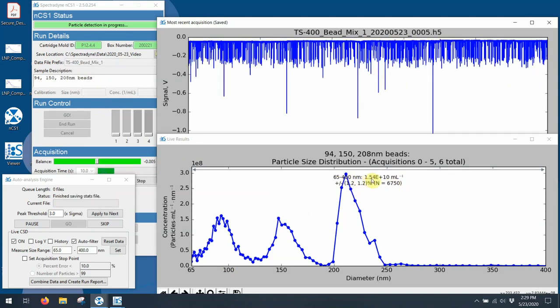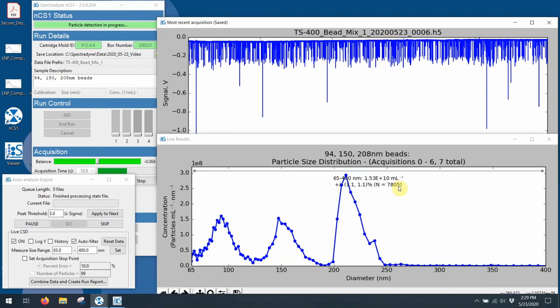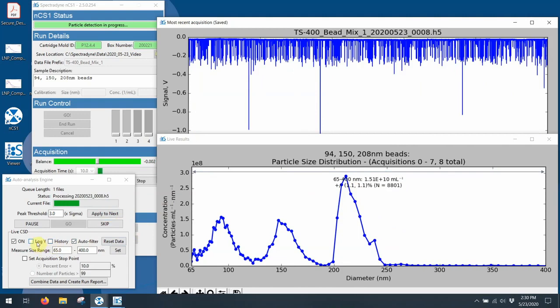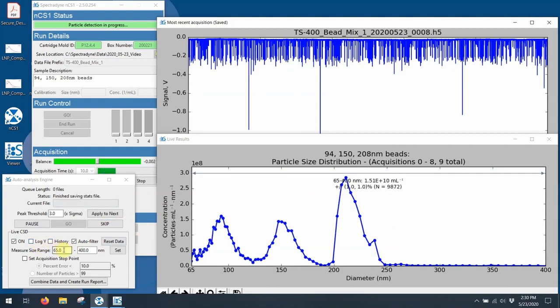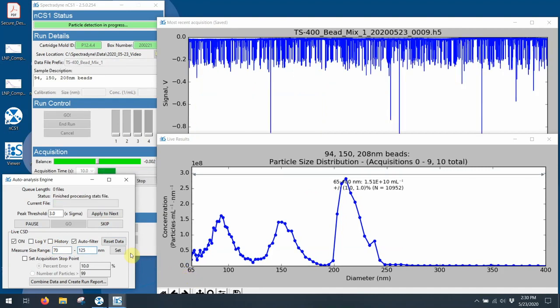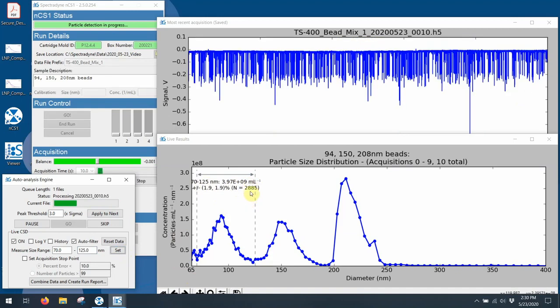Along the bottom here, you can see that it's reporting the overall concentration between 65 and 400 nanometers is 1.54 times 10 to the 10th particles per ml. That there are 6,750 particles that are included in this distribution right now. And this is our counting error, which is based on 1 over the square root of n. At any point in time, I can look at any part of this histogram and see, for instance, the exact concentration of the 94 nanometer beads merely by typing, say, 70 to 125, setting that. And now you can see that between 70 and 125 nanometers, we've got roughly 4 times 10 to the 9th particles per ml. And that there are 2,885 there.